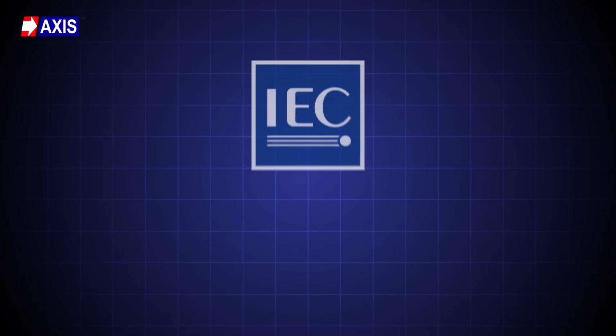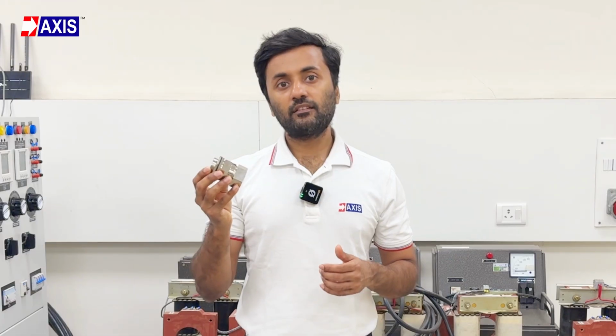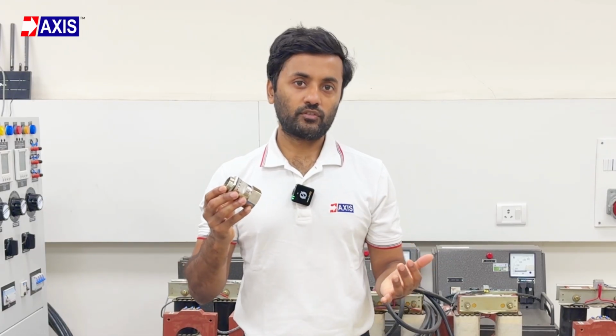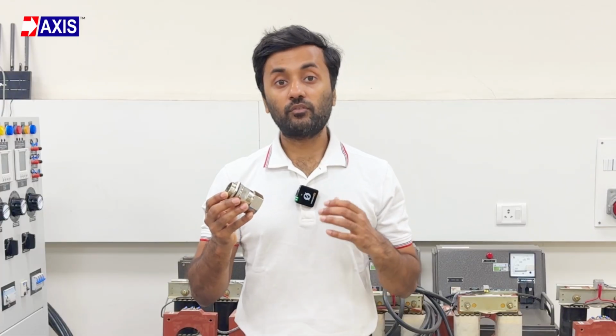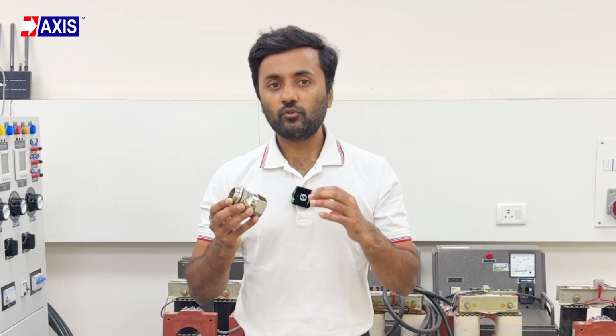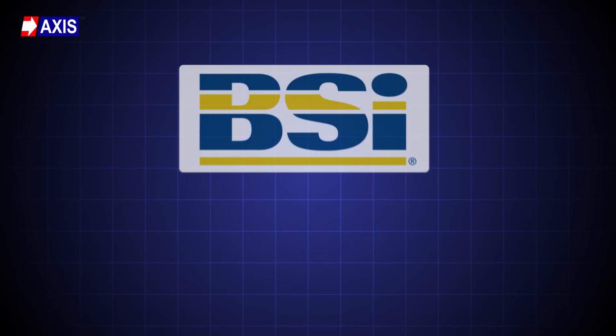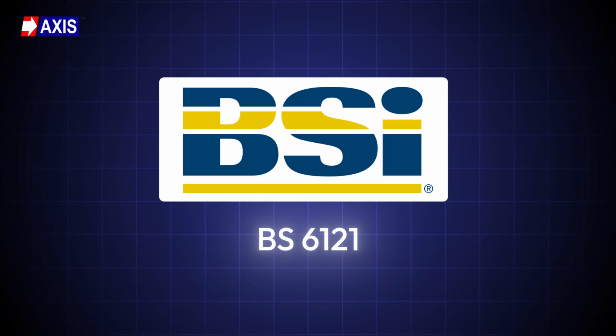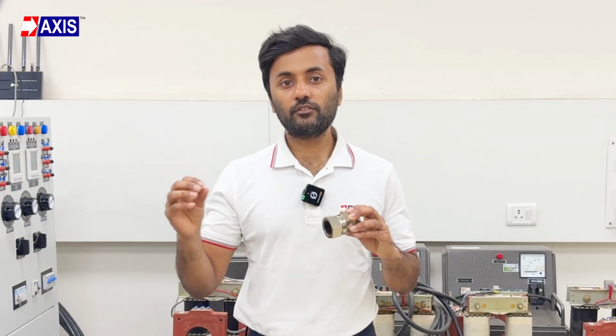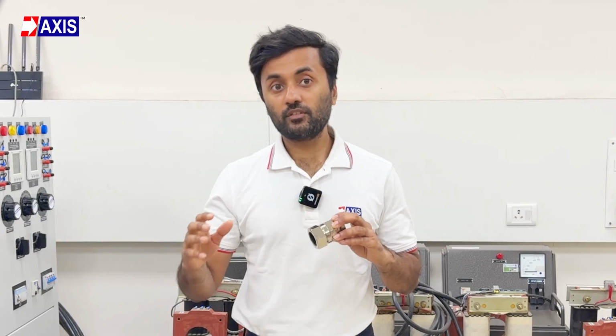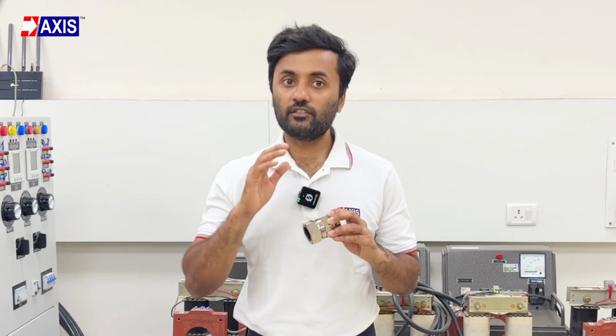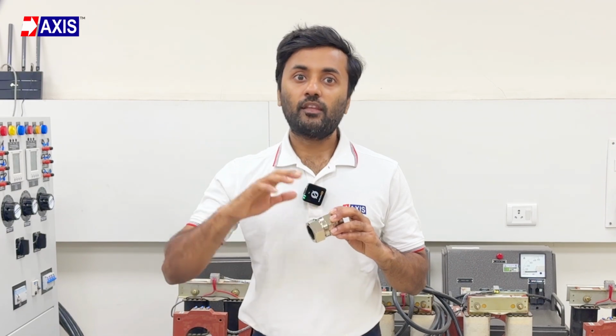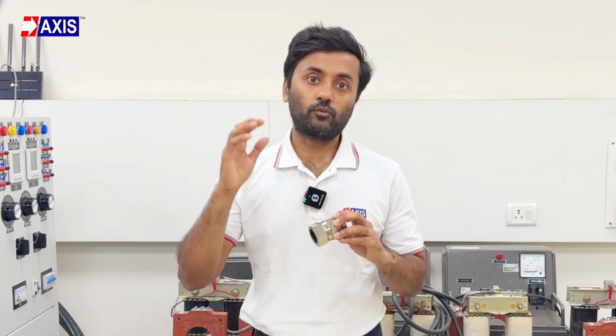Also, IEC 60529. This standard tests how well your gland seals against water and dust ingress in harsh outdoor conditions. It should have a minimum IP rating of 67. Axis glands have IP68 compliance, which provides even greater protection in submerged or extremely humid environments. BS 6121. This standard ensures armored cable glands connect armored cables to the enclosure. This testing ensures that the glands maintain mechanical integrity under installation stress. It also makes sure that the glands withstand extreme temperatures and corrosive atmospheres.